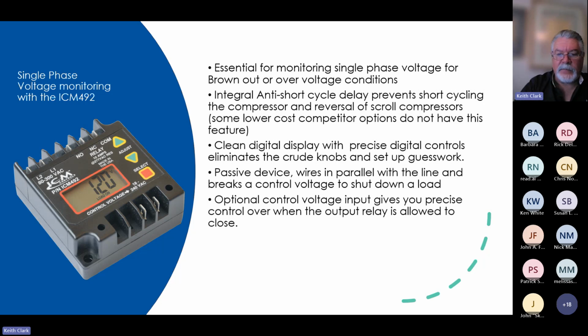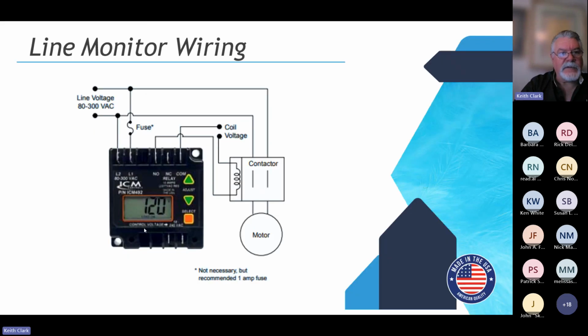And I'll show you that real. Then you can also use that relay in there. So line voltage monitoring. You've got your incoming L1 and L2. Just hooks up to L1, L2. Obviously between the disconnect and the contactor, and then this circuit here is going to basically open the contactor coil if there's a problem. So the unit has determined there's a problem. Contactor coil opens, cuts power to the system.